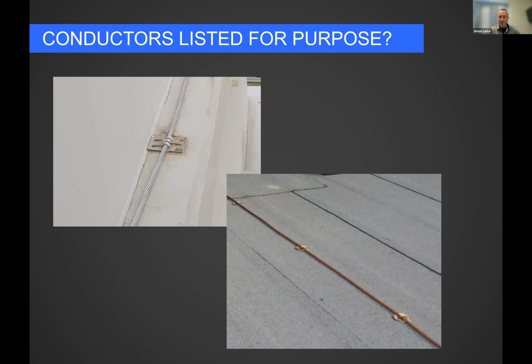So they weren't using our conductor that we'd sent them, and they didn't call us for more. They decided they'd just go out to your local e-call or EB Horsman or whoever and get themselves some aluminum grounding conductor. And then they put that in there. But the problem is that's not a listed lightning conductor. So you want to make sure it is.